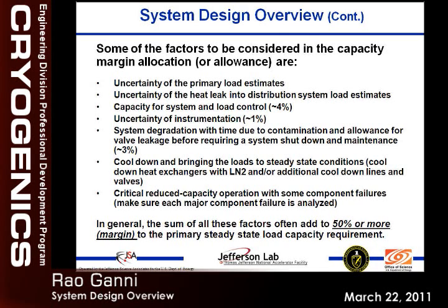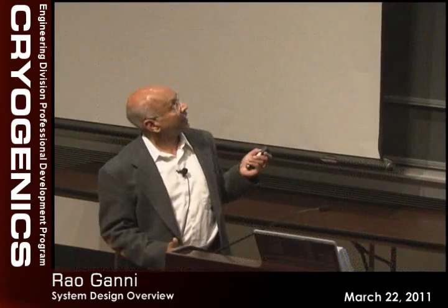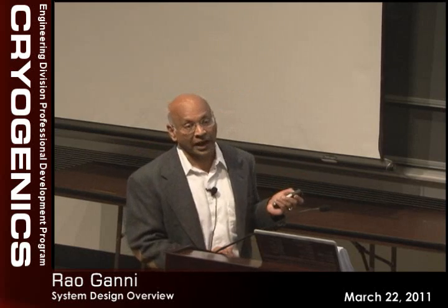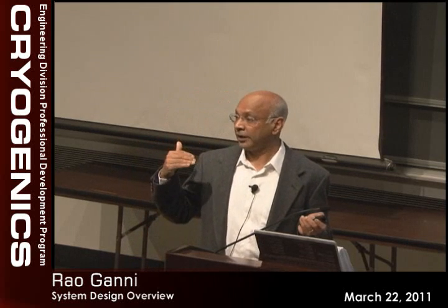Then degradation, like for example, I told you about the bypass valves on the compressors, we put in 6 megawatts of CHL, and when the cold box is not running, all the 6 megawatts are consumed on the bypass valves. They can cost you the full power, and those develop leaks over time because they're constantly working. And we won't be rebuilding, probably we get a chance every 10 years, maybe every 8 years. So we have to design our system so that a certain amount of leakage is going to happen, and it's taken into account up front in the design.